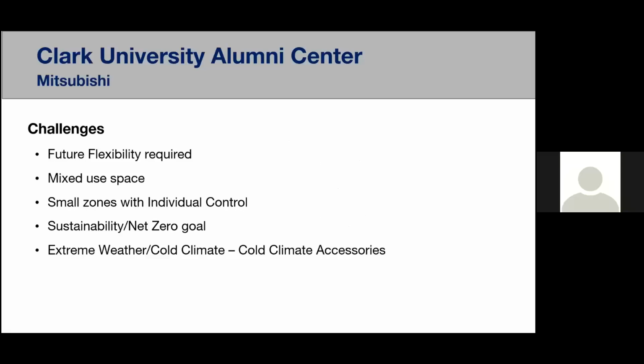If there ever was a case where you did want to combine multiple rooms into more of a conference room setting, you're able to do that and actually group those fan coils together to form one zone, so it would stay in that mode on the controller. And then mixed use space: there were a lot of different fan coils added to figure out exactly what worked best in the space as far as aesthetics. So we used ducted units, we used 1-way cassettes, we used 4-way ceiling cassettes. So basically we used all the fan coils to fit the needs in that space.